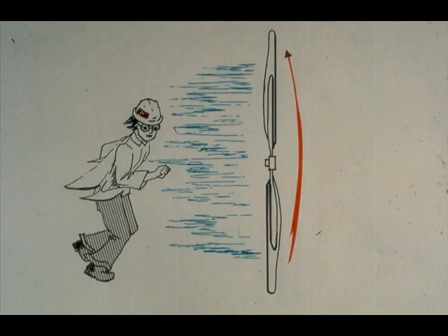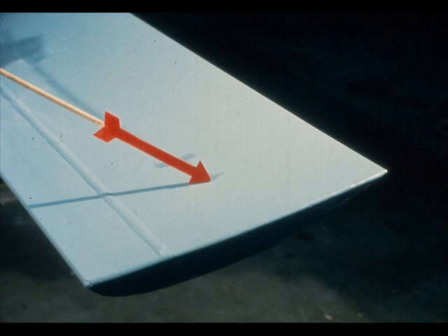Another term which is considered very important is rotation. In other words, the direction the fan rotates, clockwise or counterclockwise. It's very easy to find out by facing the fan from the air outlet or downwind side. If the fan is not moving, the downwind side is the same side of the fan as the flat side of the fan blades.